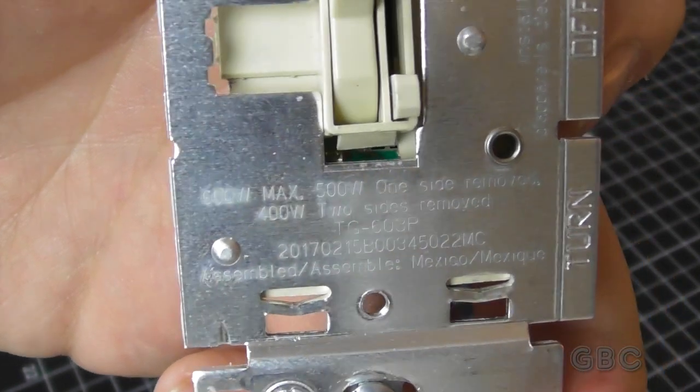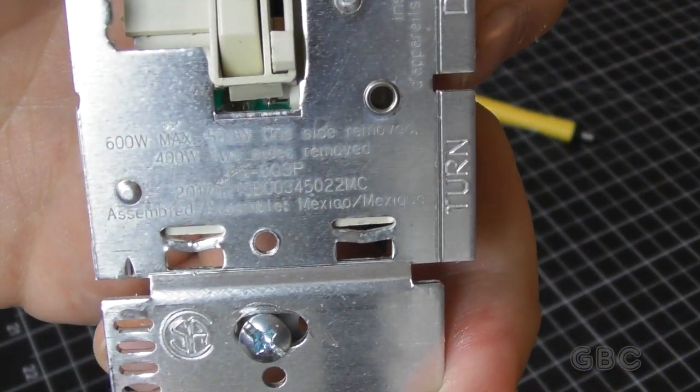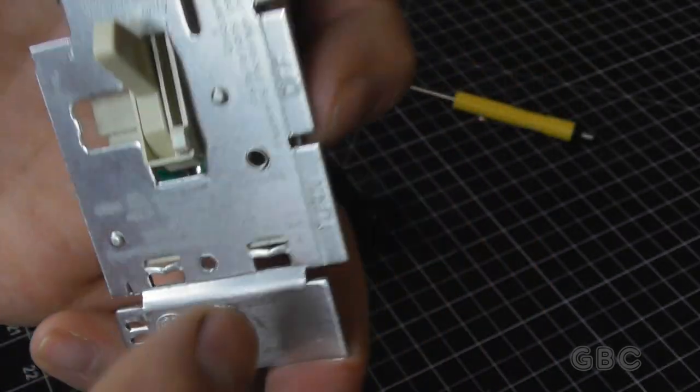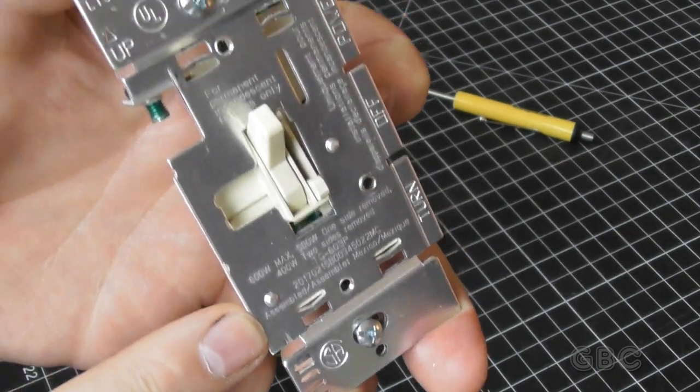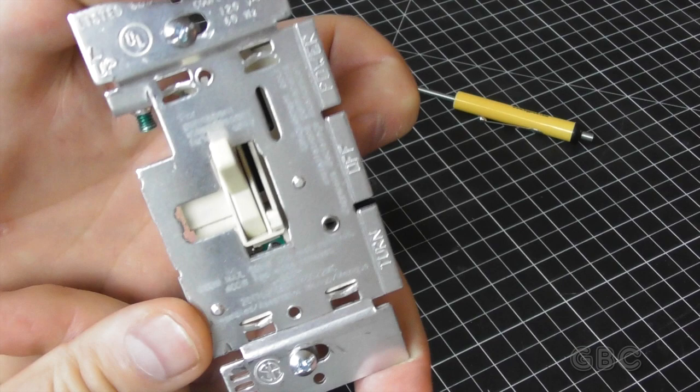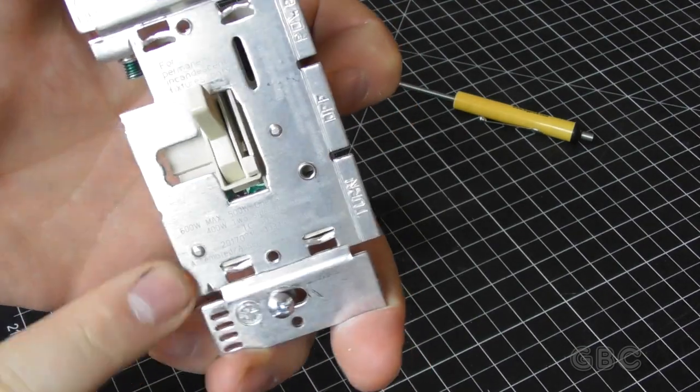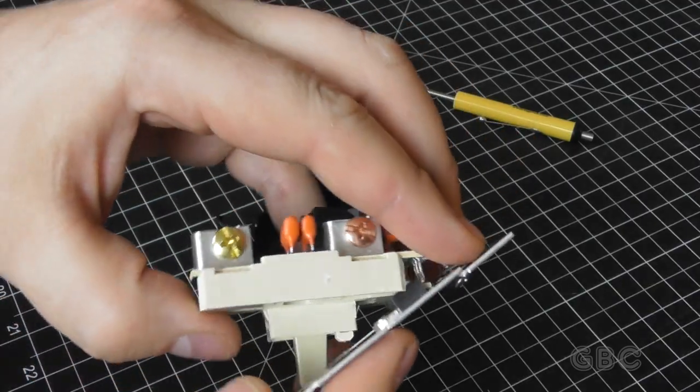It's rated 600 watts max. 500 if you remove one side and 400 if you remove both. What they're referring to are these tabs here. As you can see they are missing on this side. And in order to get this to fit in a two-gang box you have to take off the tabs on one side. So this is set up for 500 watts at this point.